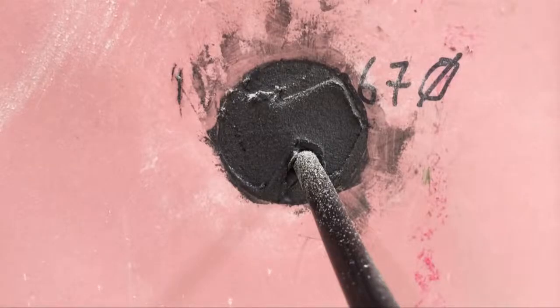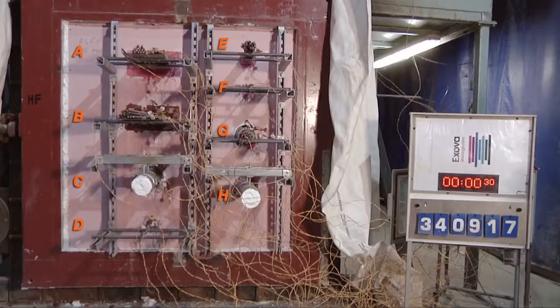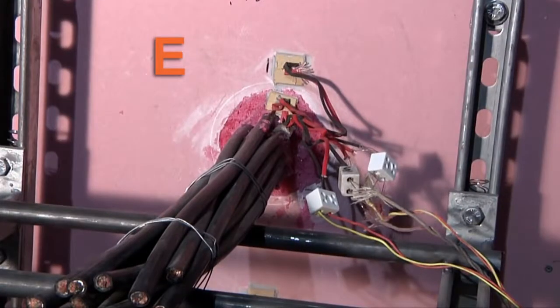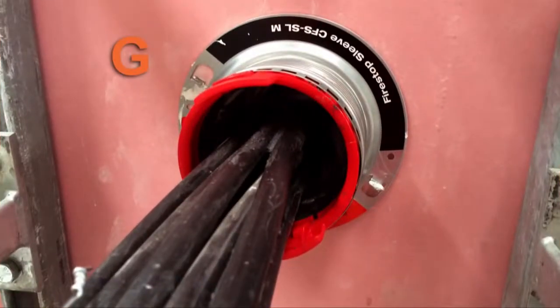Single cables: F shows a foam inappropriately used to fire-stop a single cable. D shows the same cable fire-stopped but sealed using a foam with a proven fire-resistance performance for this type of application. Bundles of cables: E shows a foam used to fire-stop a cable bundle, and G shows a cable bundle protected with a sleeve device of proven fire-resistance performance.